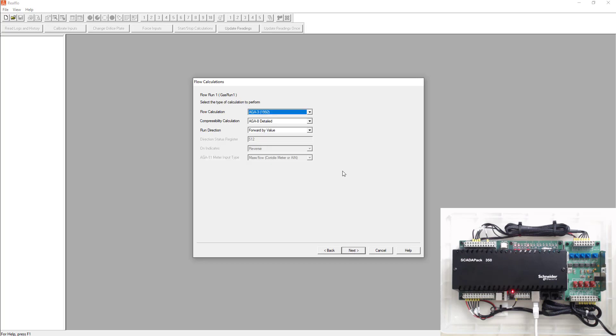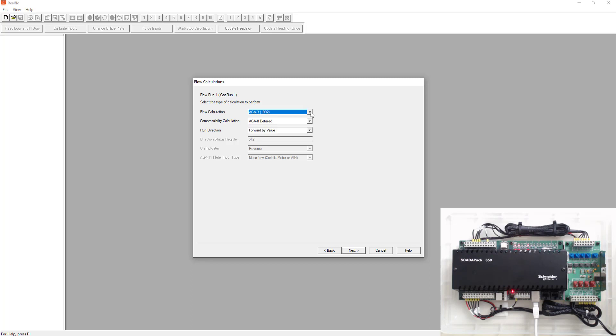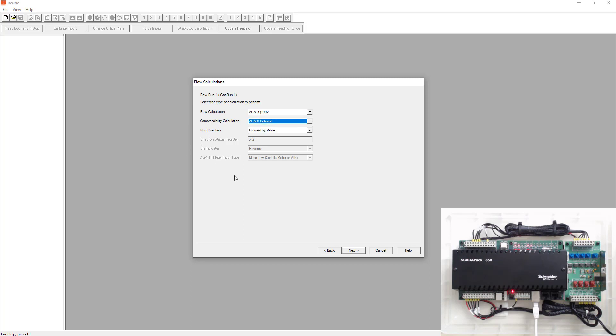Next it's going to ask you what type of flow calculation do you want to use. You want to use AGA3, 7, 11 or V cone. We're going to simulate an AGA3 calculation. So an orifice plate calculation. What's your compressibility calc? We're going to use AGA8, but you could use NX19. Run direction. It's going to be forward by value. You can set up two flow runs, a forward by value and reverse by value if you're loading and unloading a tank. But for this application, we're just going to use forward by value.